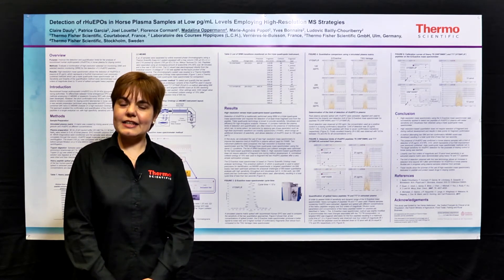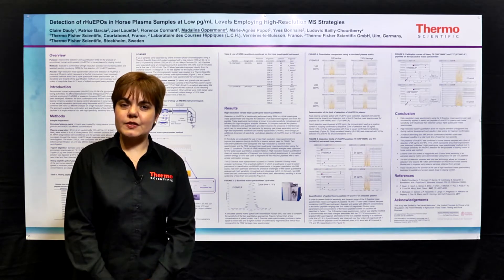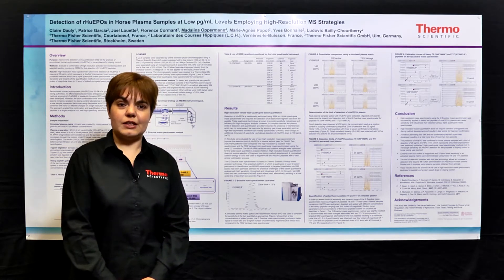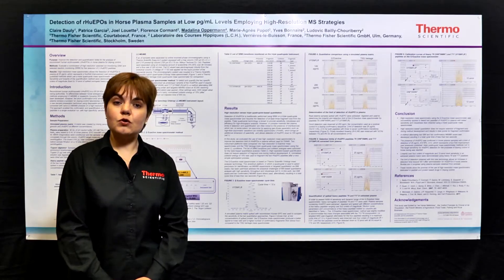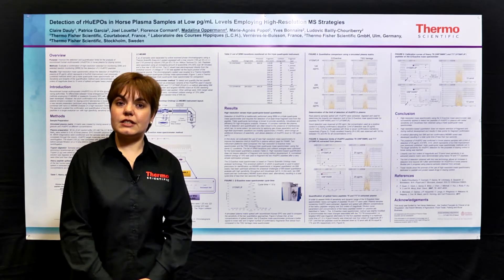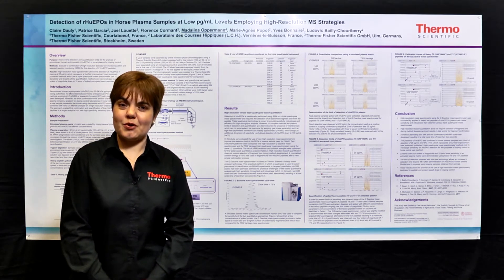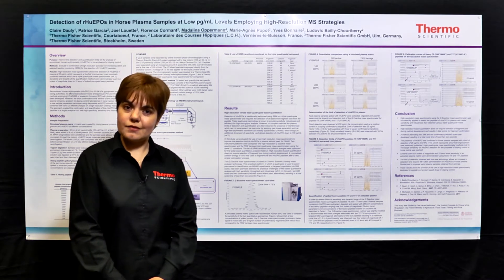In this particular case, we found that the high-resolution mass spectrometry platform, the Q Exactive, was offering superior performance due to its high-resolution capability. The way we were employing the Q Exactive was to have a high-resolution selected ion monitoring scan at 140,000 resolution, followed by targeted HCD scans for the respective peptides used for confirmatory purposes. In this way, we were achieving a higher level of performance.